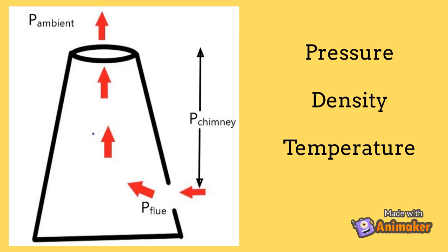Let us explore the root cause. The flue gas is generally the end product of some process — may be combustion, incineration, or some chemical reaction — so it is generally at a higher temperature compared to the ambient air. This temperature difference induces a difference in density between the flue gas and the ambient air, and because of this density difference, a pressure difference is created. This pressure difference is responsible for the flow of flue gas from the bottom part of the chimney to the topmost part, so that it can get easily dispersed with the atmospheric air.